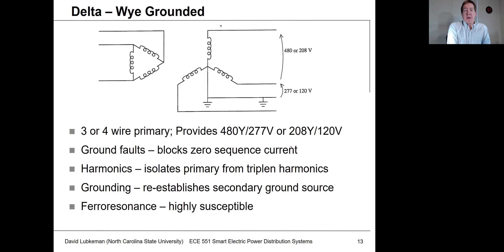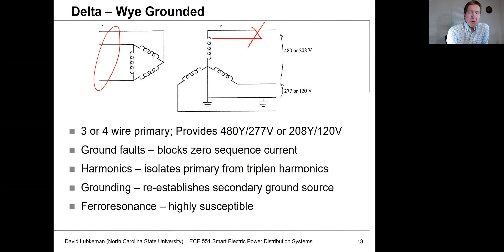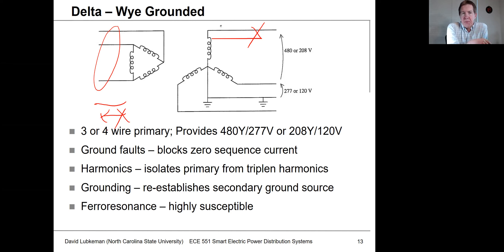Another option is a delta/Y-ground connection. The primary can be three-wire or four-wire (without using the neutral). This can also be used for providing 480 volts or 208 volts line. In this case, if you had a short circuit on the secondary, all currents must sum to zero on the delta side — so you get no zero-sequence current, meaning you would not see a ground fault current through any neutral on the primary side. This connection effectively blocks zero-sequence current, which may be good or bad depending on your application.